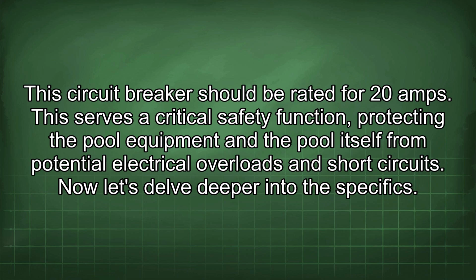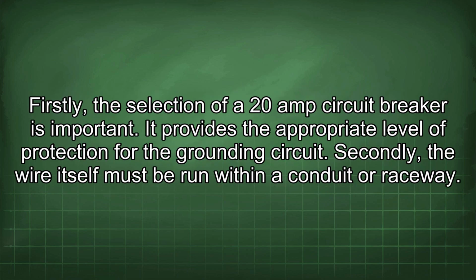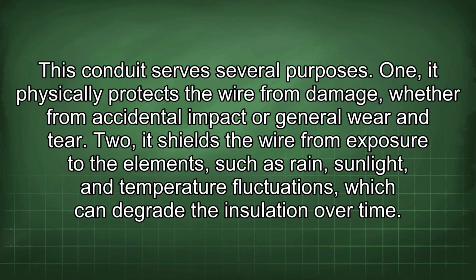This serves a critical safety function, protecting the pool equipment and the pool itself from potential electrical overloads and short circuits. Now let's delve deeper into the specifics. Firstly, the selection of a 20 amp circuit breaker is important. It provides the appropriate level of protection for the grounding circuit. Secondly, the wire itself must be run within a conduit or a raceway. This conduit serves several purposes.